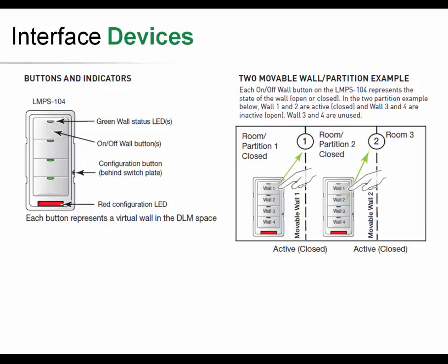Subsequent pushes, it's going to be about a 3-second push to activate the wall. It's to be able to turn these on and turn these off. If we've got multiple LMPS-104s, we're going to have to go through on each switch and enable the walls so that they can later be activated.